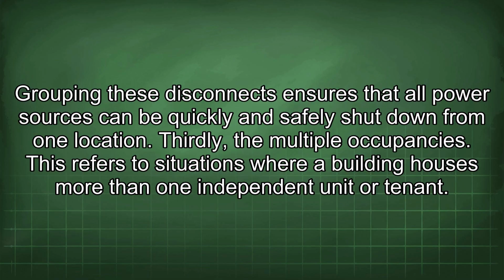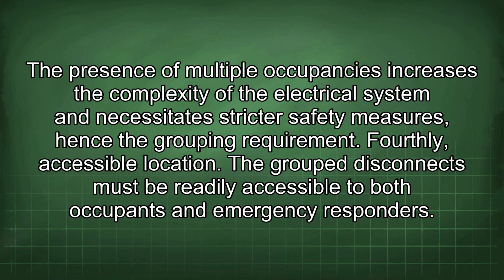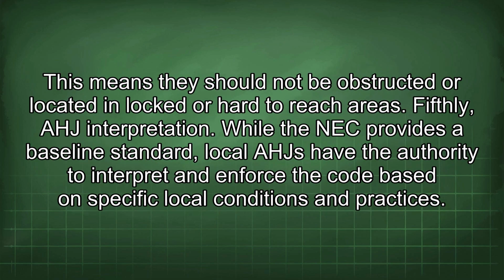Thirdly, the multiple occupancies. This refers to situations where a building houses more than one independent unit or tenant. The presence of multiple occupancies increases the complexity of the electrical system and necessitates stricter safety measures, hence the grouping requirement. Fourthly, accessible location. The grouped disconnects must be readily accessible to both occupants and emergency responders. This means they should not be obstructed or located in locked or hard-to-reach areas.